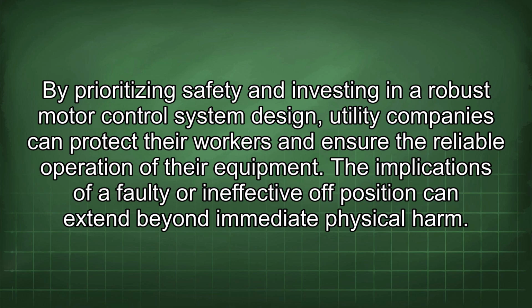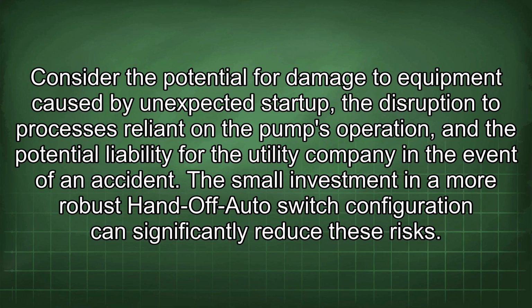The implications of a faulty or ineffective off position can extend beyond immediate physical harm. Consider the potential for damage to equipment caused by unexpected startup, the disruption to processes reliant on the pump's operation, and the potential liability for the utility company in the event of an accident. The small investment in a more robust hand-off-auto switch configuration can significantly reduce these risks.